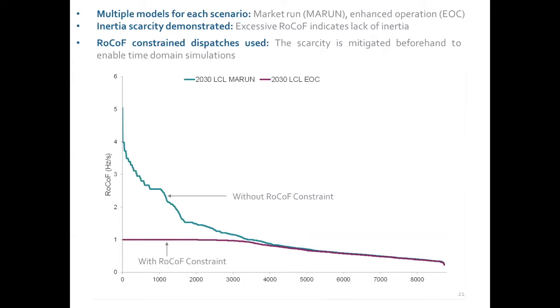So to mitigate against this scarcity, a RoCoF constraint was introduced in the unit commitment, which uses the dimensioning event and system rotational energy to calculate and also limit the RoCoF values. It can be seen in the figure that the effect of the constraint ends up limiting the rate of change of frequency to 1 Hertz per second.